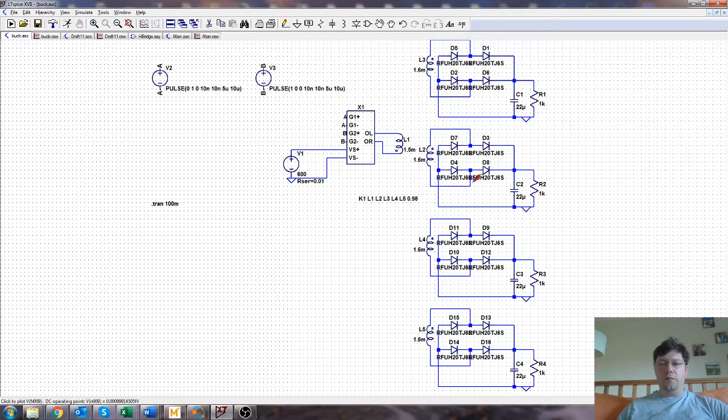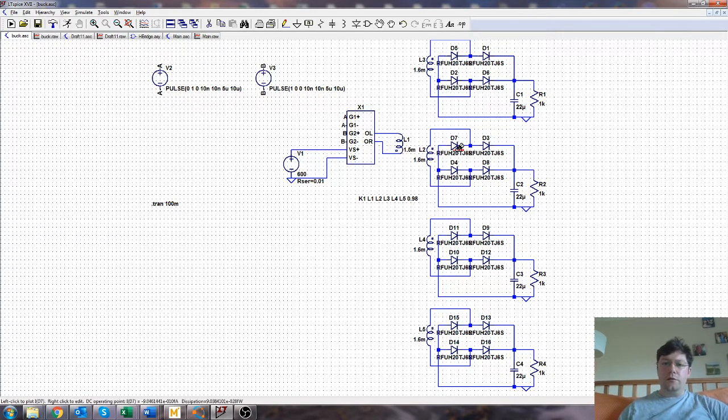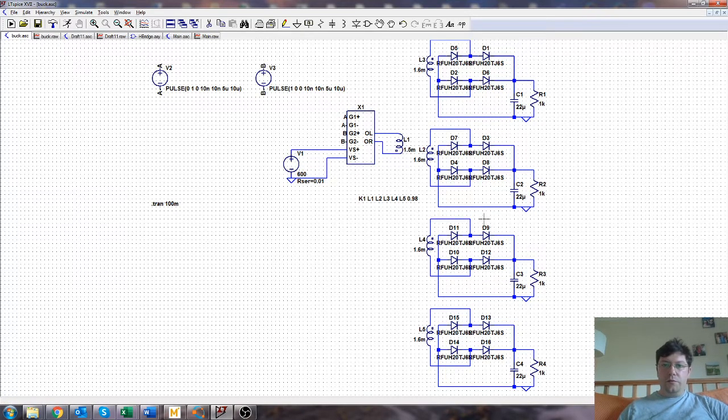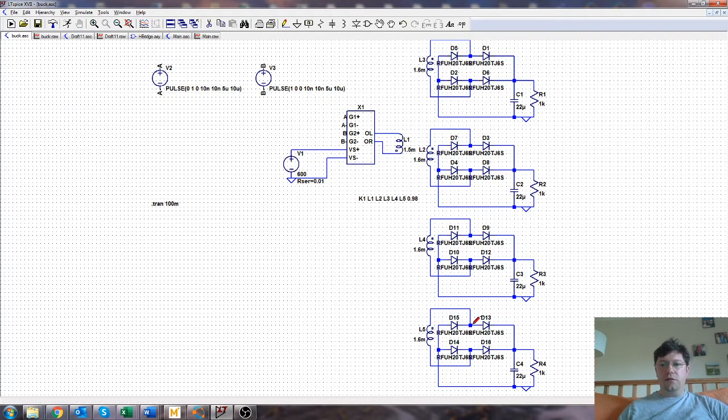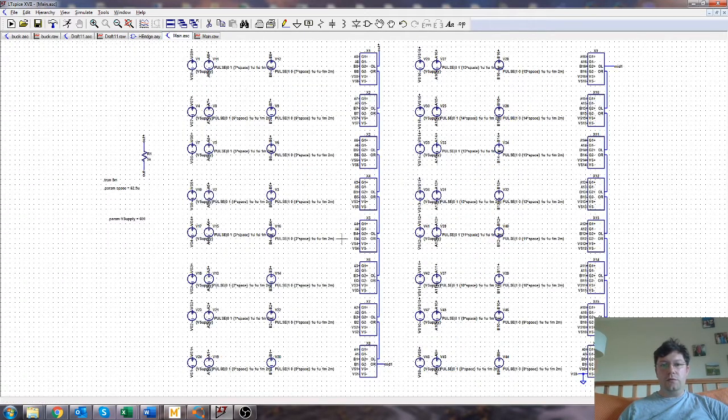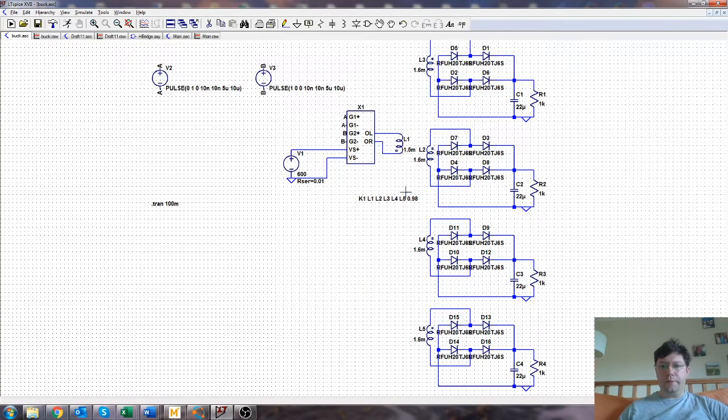And then you could have a number of outputs per phase. As long as you've got the same number of outputs per phase, then you should have a reasonable balance in your power system. Of course, if you did have three phases and used this circuit as is, you'd only get 12 outputs. But you need 16 outputs for here. So some adjustment would be required there.